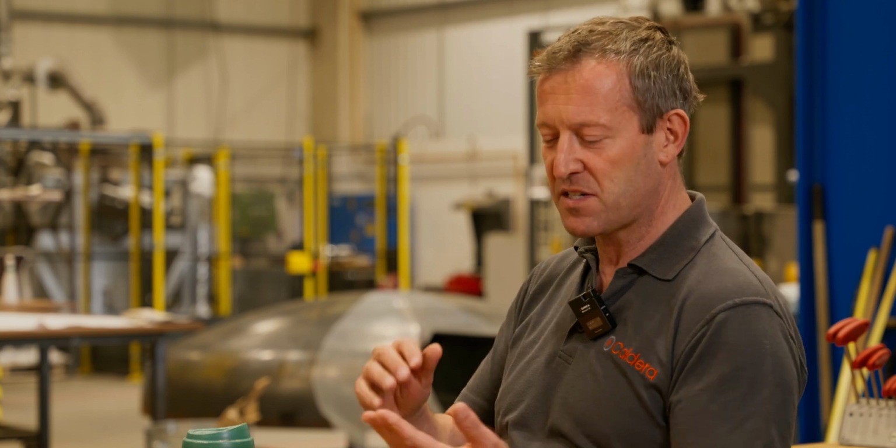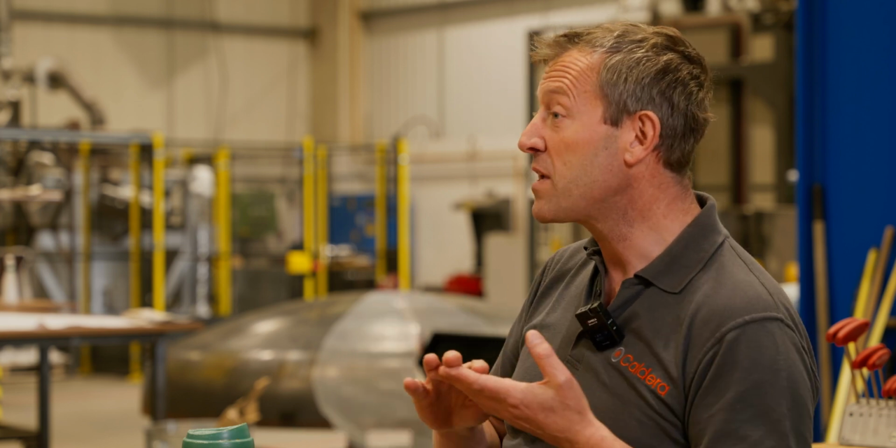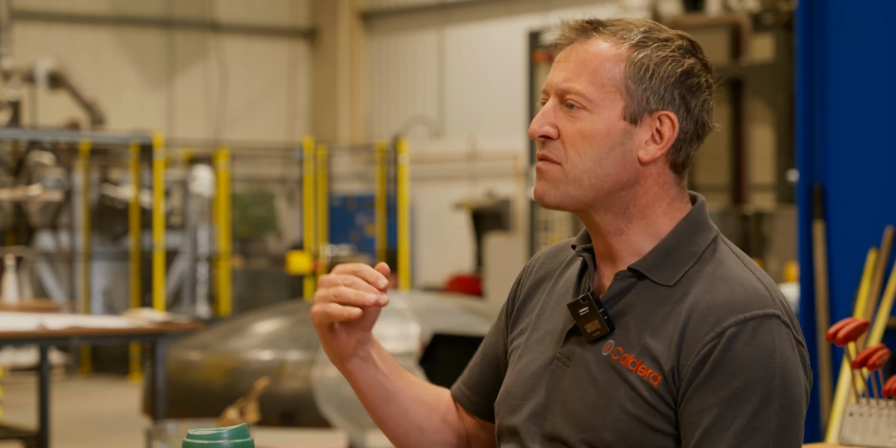One last very quick technical question. What's the reason for the capping at 500 degrees? Everything gets expensive above 500 degrees. So steels, you need higher quality steels. Things start to creep.